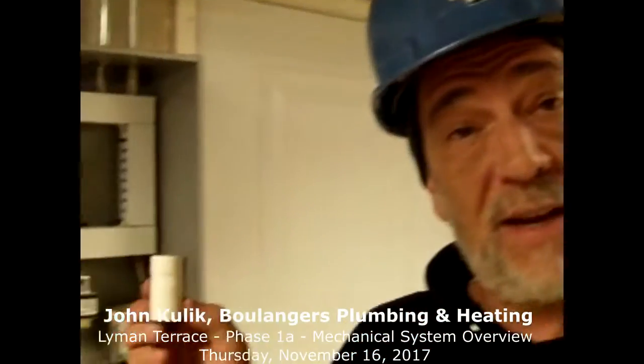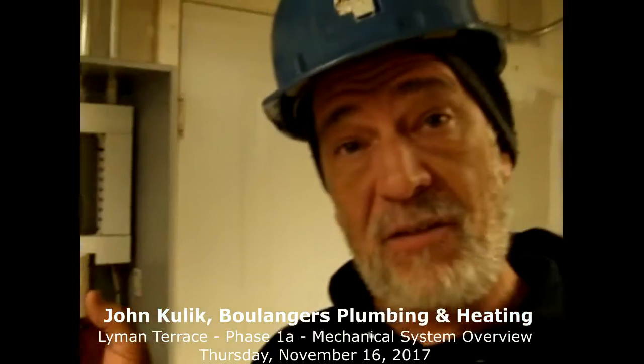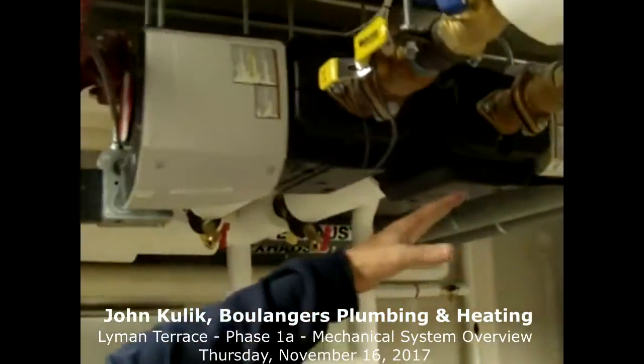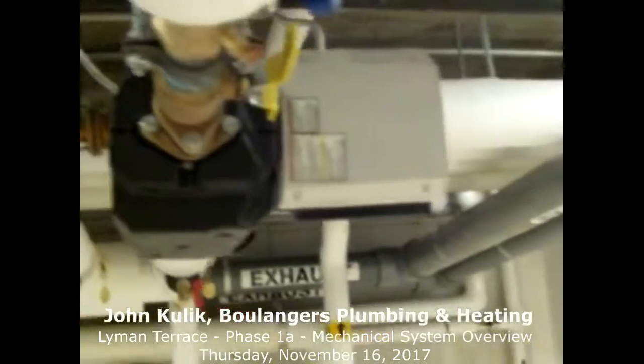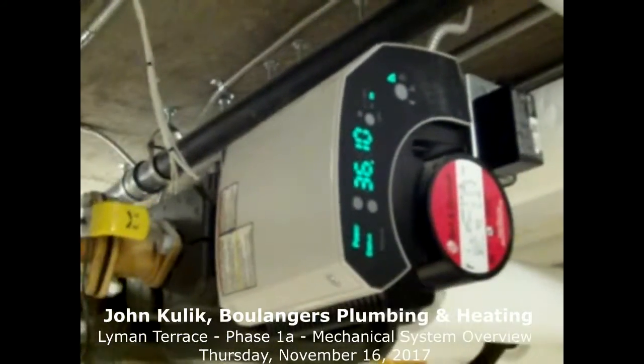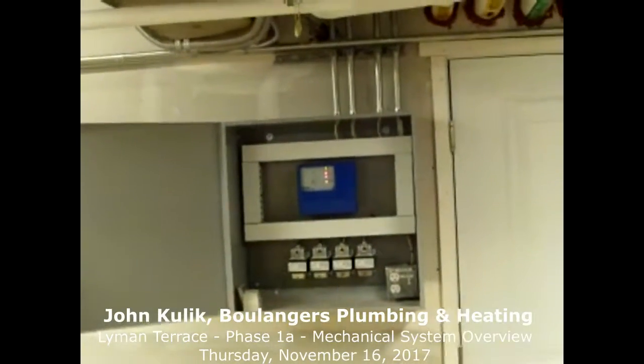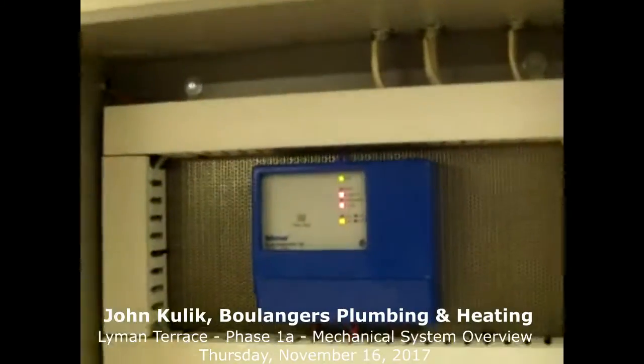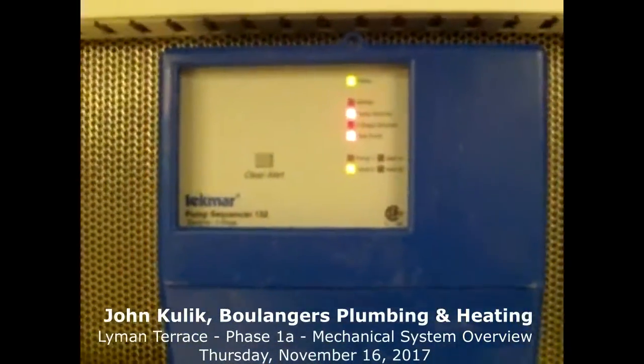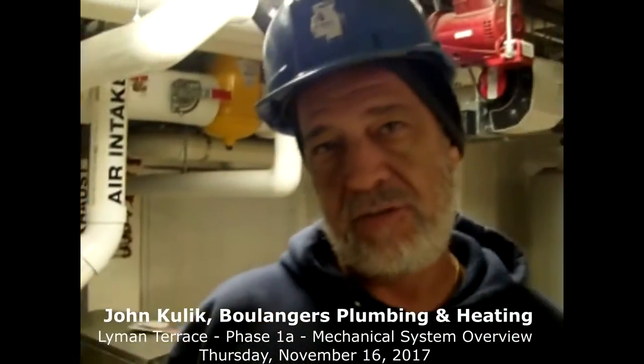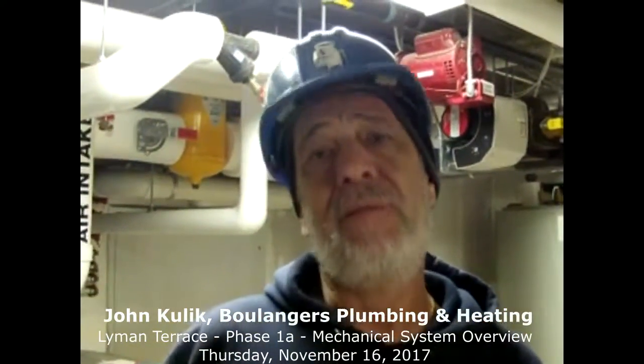Okay, so first thing that happens is the outdoor temperature falls. It activates the system to come on, turns on the main circulator pumps we see here. There's redundant operation here as a backup. These are the main heat loop circulator pumps. Yep, variable speed. Those are magnetic drive pumps. Those are controlled by the Tekmar pump controller mounted in the panel. Which is the little blue box, right? Correct. Okay. And that blue box will flash codes to tell you if there's a problem with one of the pumps or both pumps. That's one of the items that should be looked at weekly by maintenance. Open the panel, make sure nothing's flashing so that they can call and have service performed before a major emergency.